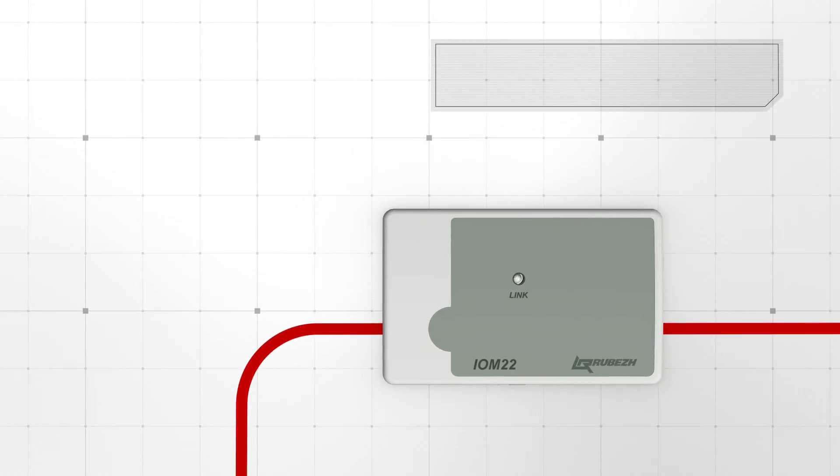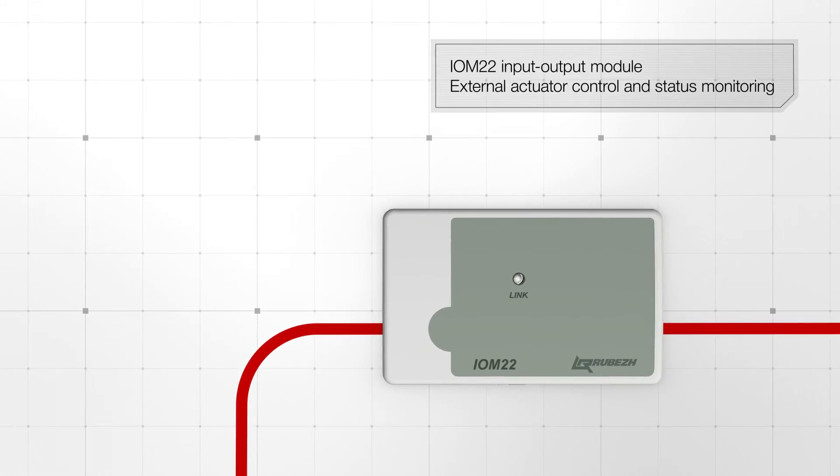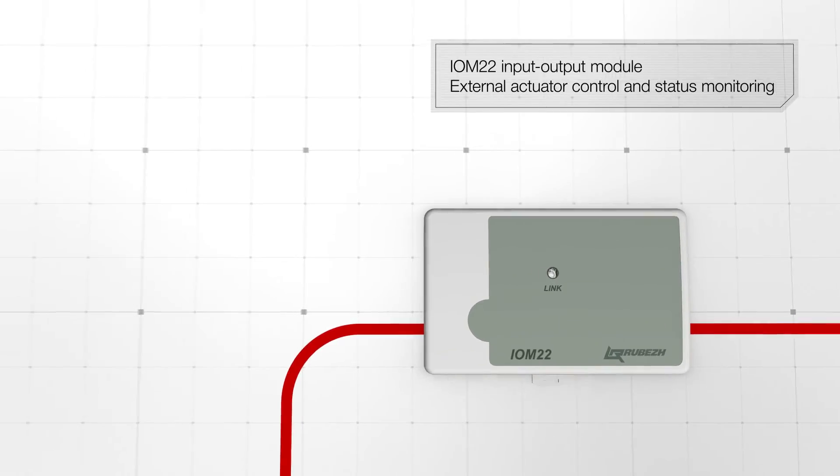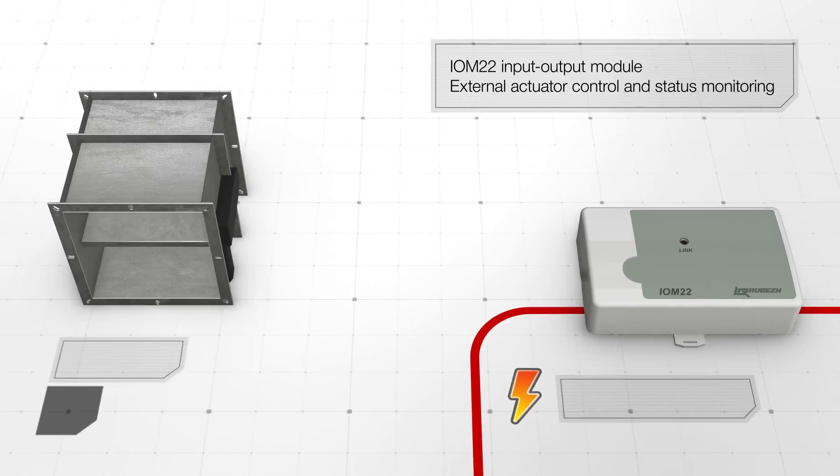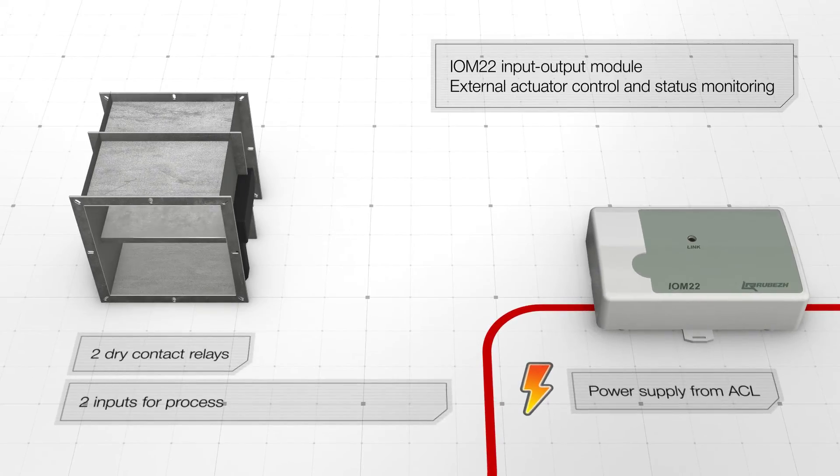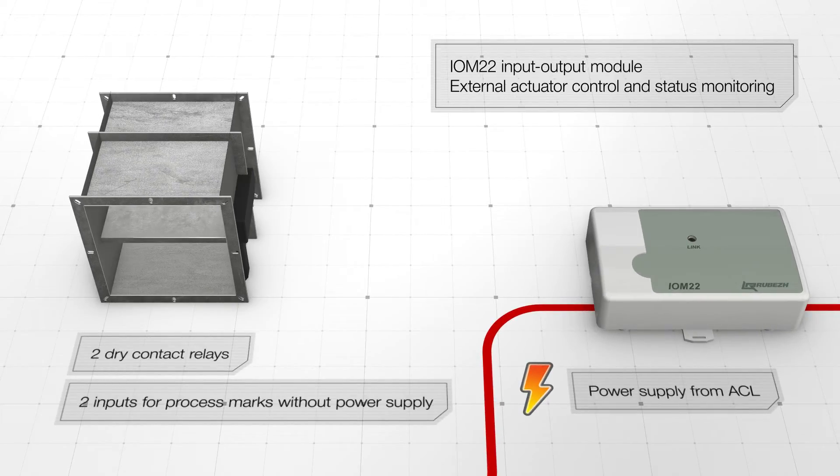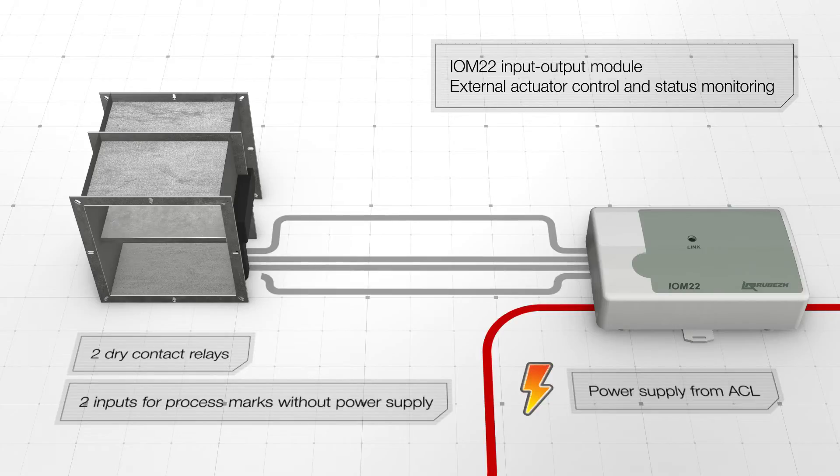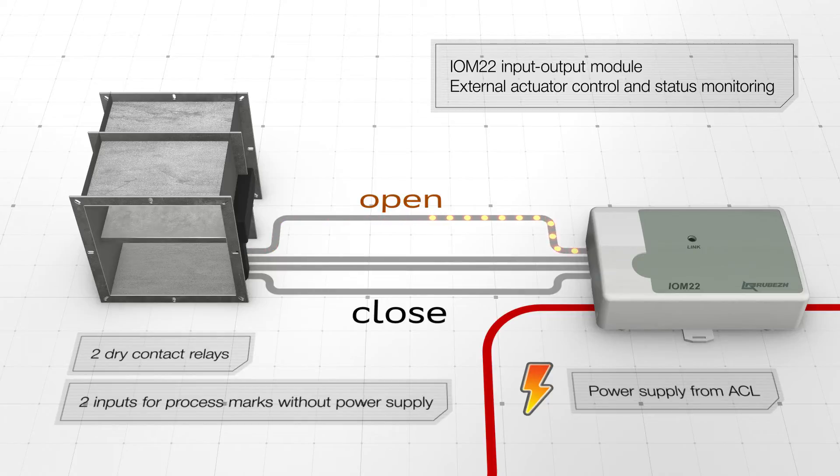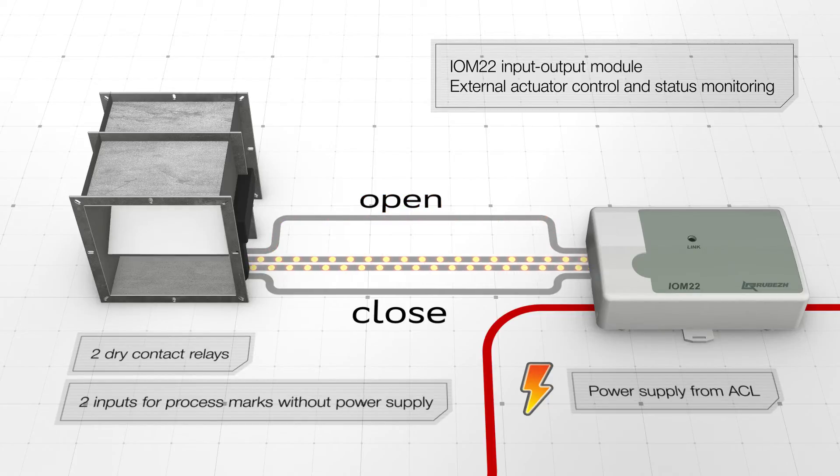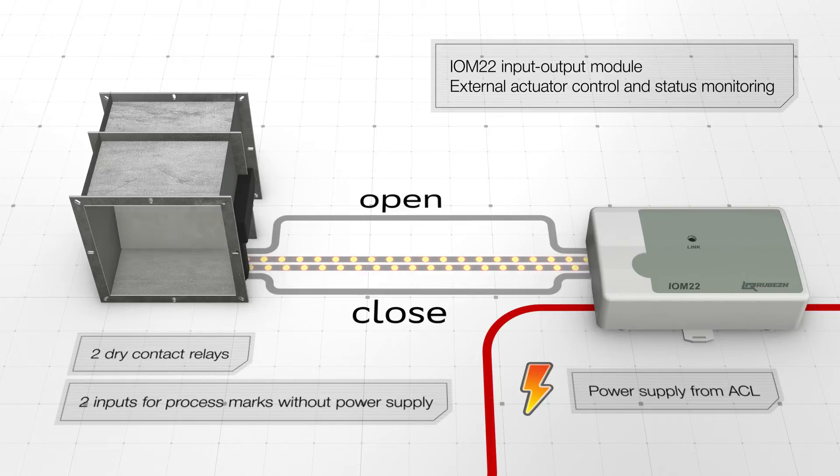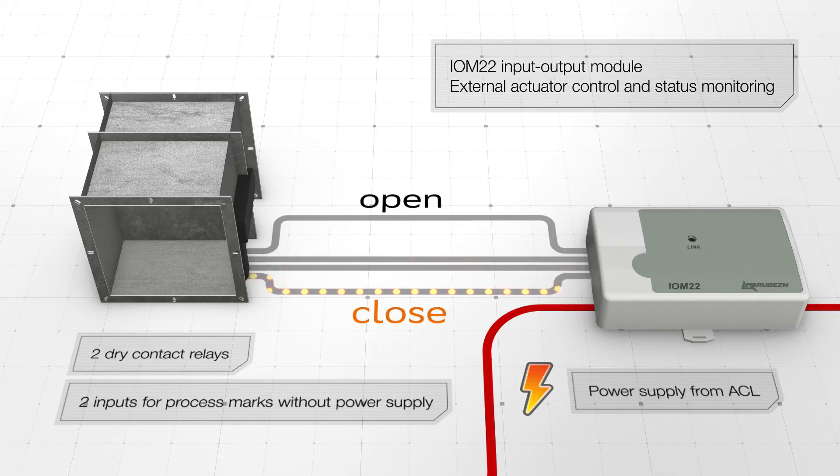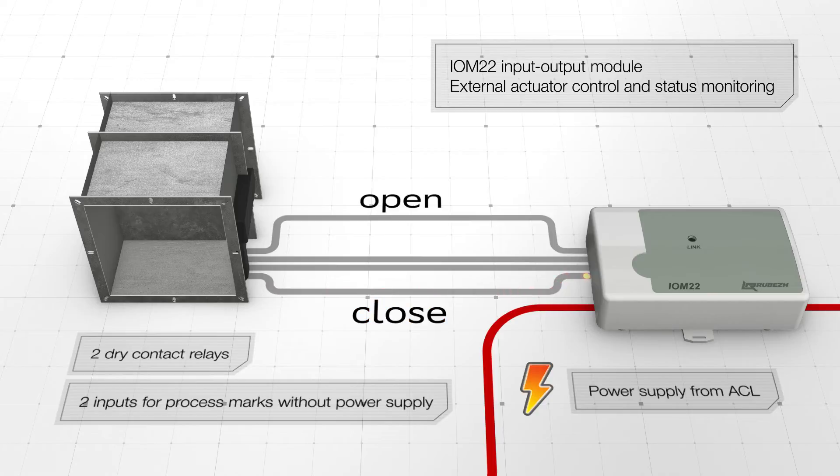IOM22 input-output module is used to control external actuators and to monitor their status using two inputs. IOM22 input-output modules are powered through the addressable communication line. One example of IOM22's application is smoke exhaust valve control with position monitoring. IOM22 comprises two dry contact relays and two inputs for process modules connection without power supply.